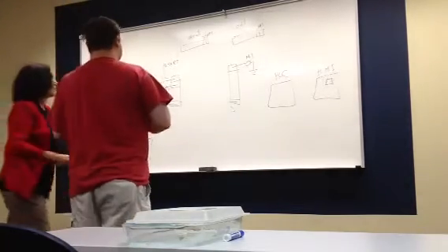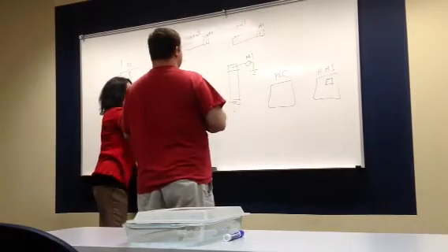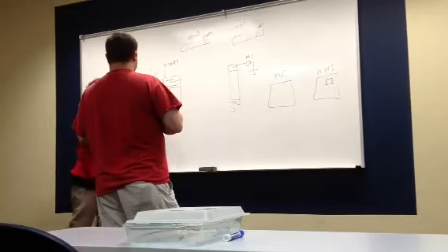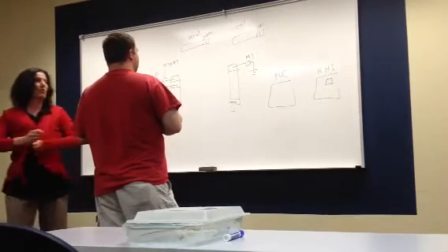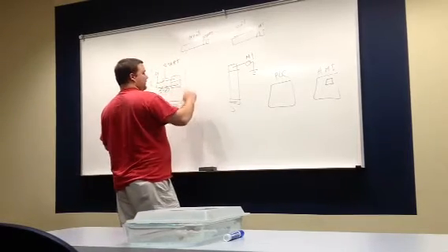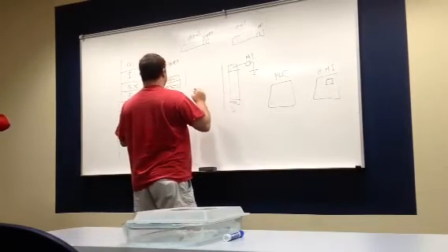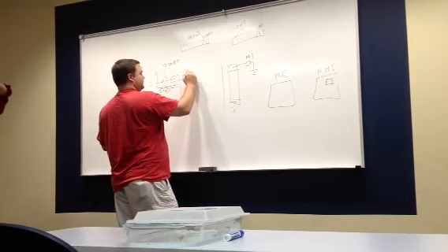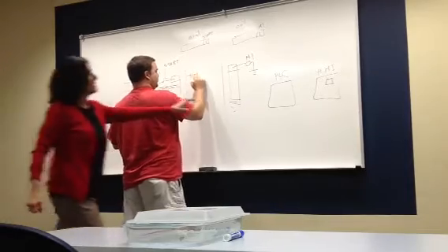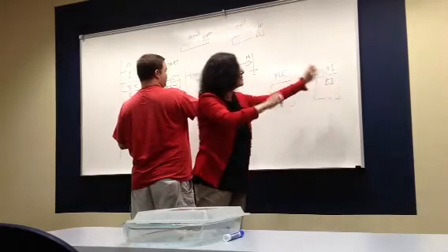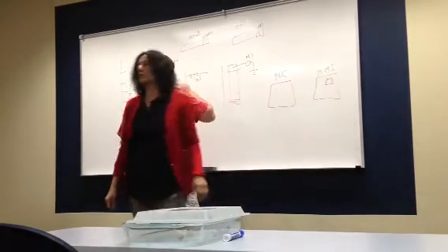If the motor output is true and you did not receive the input, choose any O, any R, it doesn't matter. O colon 2/3 for the motor. You understand? If the motor output is true and we don't receive the input in 5 seconds, we're going to send the signal to the operator interface remotely. It might be in another city, like in the irrigation system. Flash red: motor, fail to start.